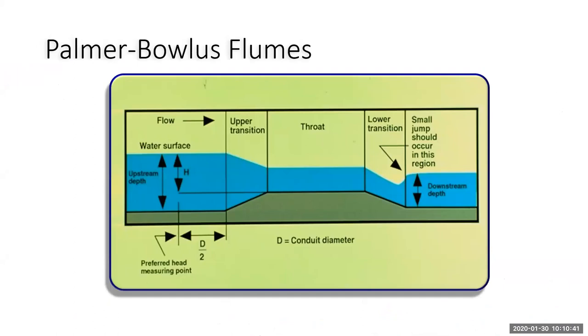Other types of flumes are the Palmer Bowlus flume. This is a little bit different. The water goes through the flume. We're concerned about the water going over the top of the flume. But what makes this different is that it has that upper transition. We have the arrow pointing to the zero point. At the top of that upper transition is the zero flow. That's where we want to calibrate the level from the zero point up to the water surface.